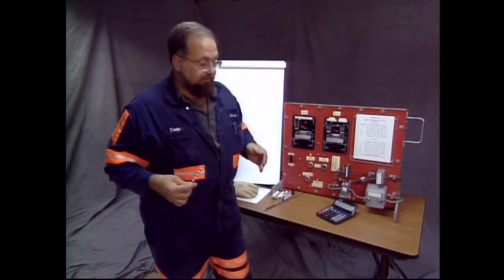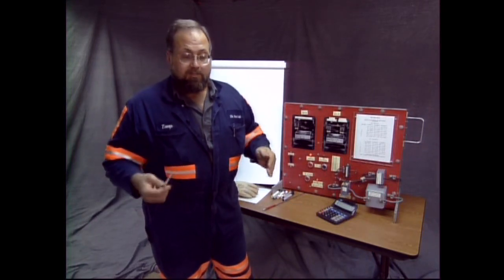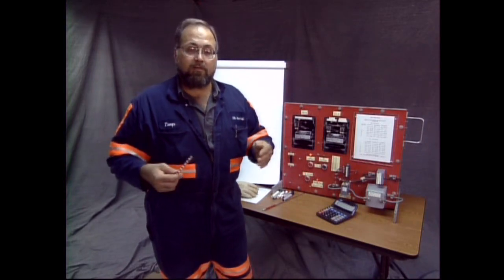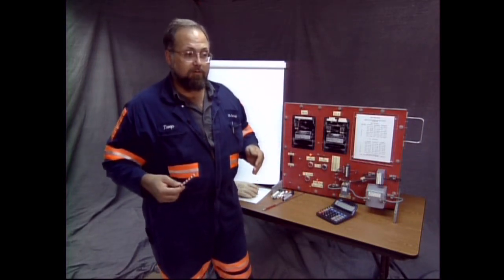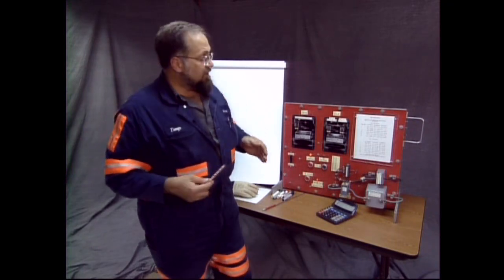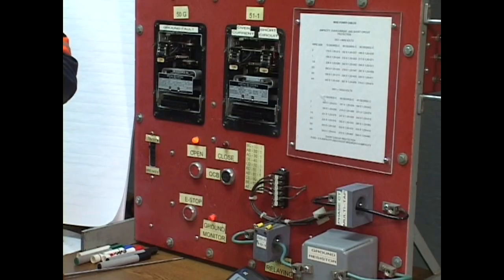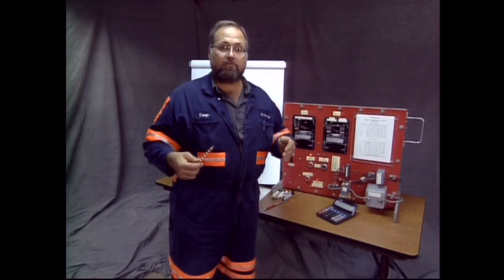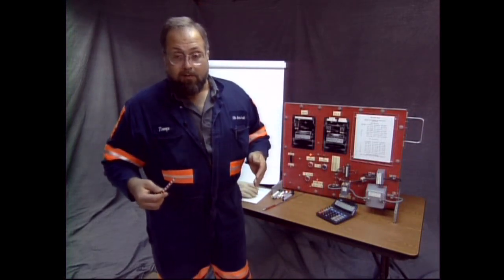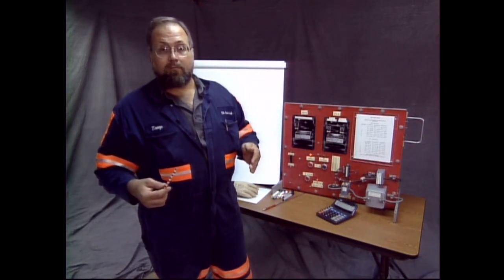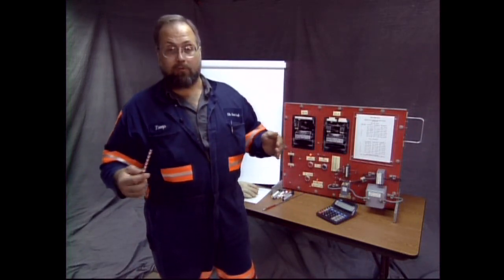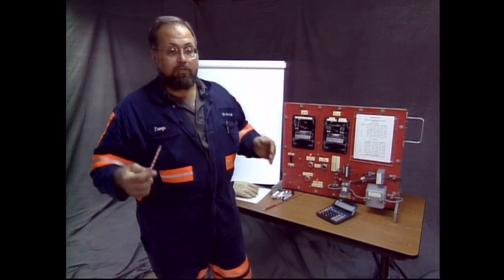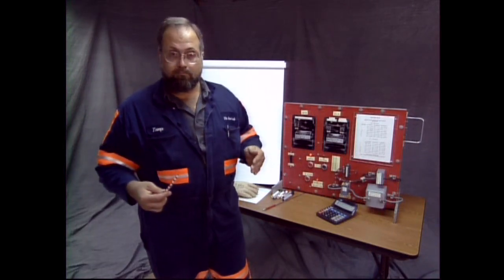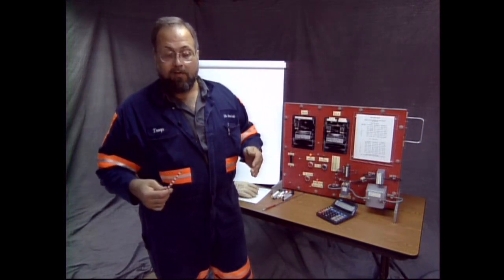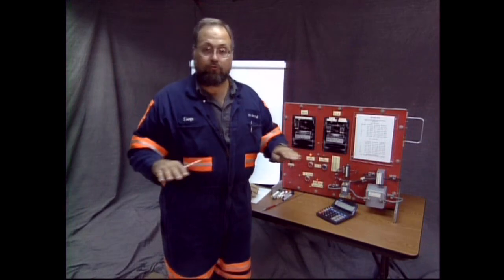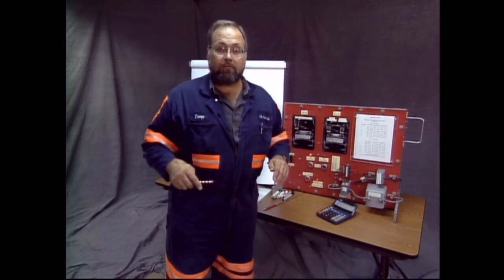Now, after you take the power off, after you lock and tag, it's not considered to be disconnected and locked and tagged and ready for work on a high voltage circuit until you ground it. These phases, you know, cables have the capability of storing electricity as a capacitor would. Transformers, dry type transformers, they have the capability of storing electricity as a capacitor would. Some high voltage circuits have actual capacitors on them. Until you shunt these phases both to each other and to the ground and make everything the same potential, everything is neutral now, they're grounded, it's not safe. It's not safe.